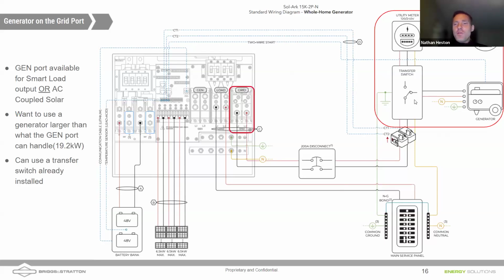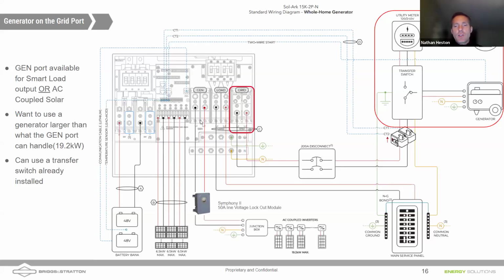I've been sick. You would need to do that through the grid port. And so showing that, that would be coming through a transfer switch. And a nice thing that this does is it leaves that generator port open, and you could use that as a load output as well. So that's a nice feature. You could also use it to bring in AC coupled solar.